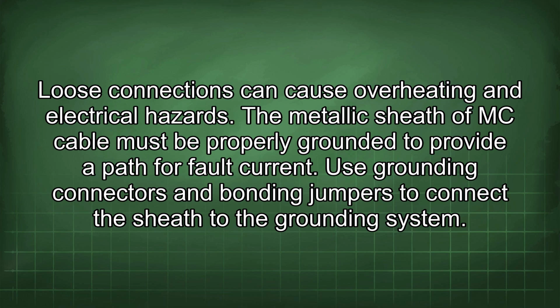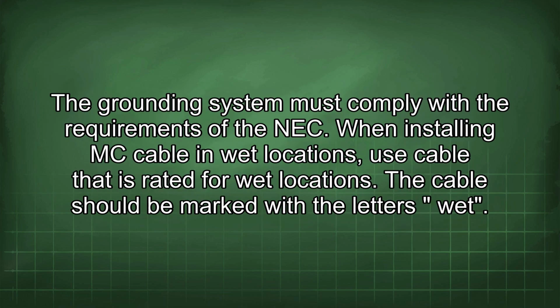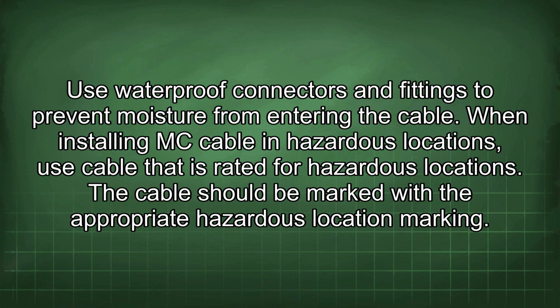The metallic sheath of MC cable must be properly grounded to provide a path for fault current. Use grounding connectors and bonding jumpers to connect the sheath to the grounding system. The grounding system must comply with the requirements of the NEC. When installing MC cable in wet locations, use cable that is rated for wet locations. The cable should be marked with the letters WET. Use waterproof connectors and fittings to prevent moisture from entering the cable.